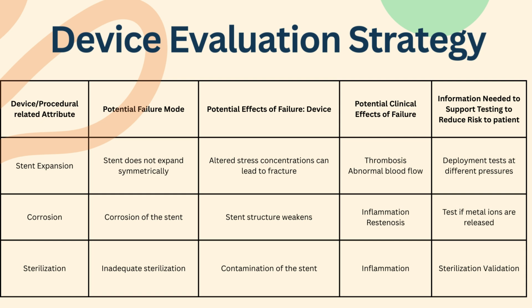Another problem that could happen with the device is corrosion of the stent specifically. This would weaken the structure of the stent, and this could cause inflammation and restenosis. To avoid this, we would have to test whether metal ions are being released so that we could avoid inflammation or restenosis. Another problem that we could have is inadequate sterilization. That would lead to contamination of the stent, leading to inflammation. So we would have to do sterilization validation so that we could avoid this inflammation in the patient.